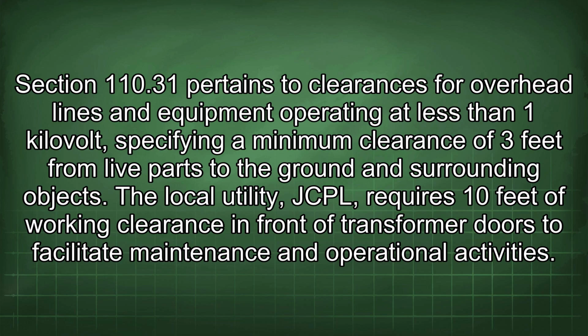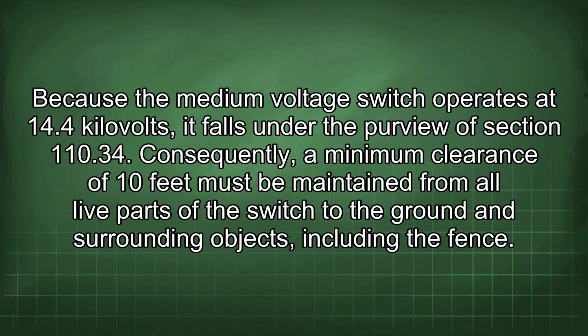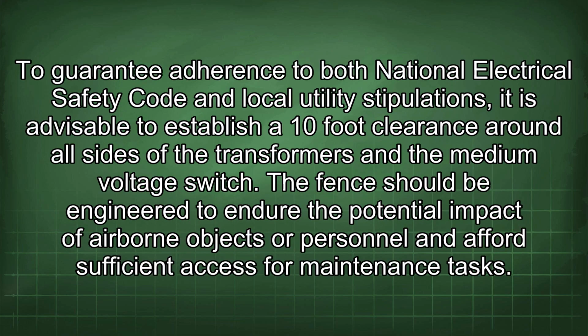The local utility, JCPL, requires 10 feet of working clearance in front of transformer doors to facilitate maintenance and operational activities. Because the medium voltage switch operates at 14.4 kV, it falls under the purview of Section 110.34. Consequently, a minimum clearance of 10 feet must be maintained from all live parts of the switch to the ground and surrounding objects, including the fence. To guarantee adherence to both the National Electrical Safety Code and local utility stipulations, it is advisable to establish a 10-foot clearance around all sides of the transformers and the medium voltage switch.